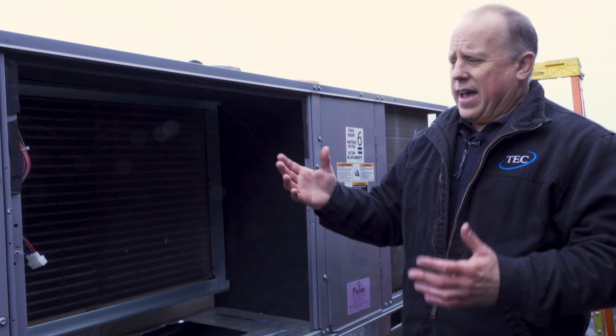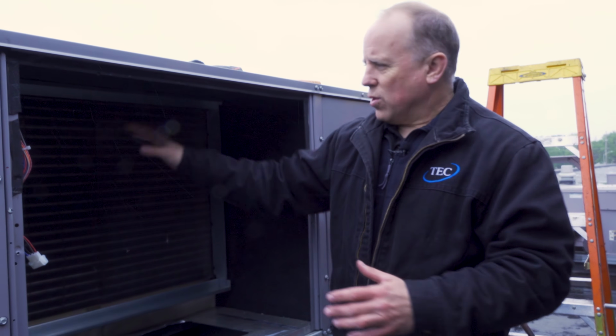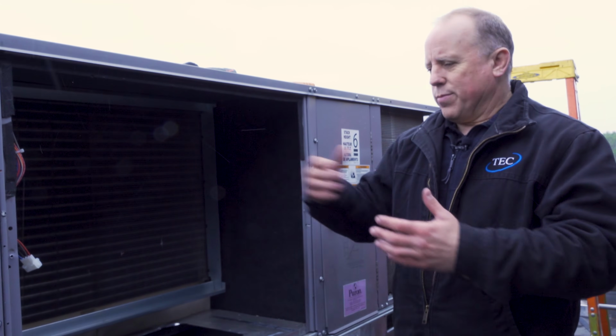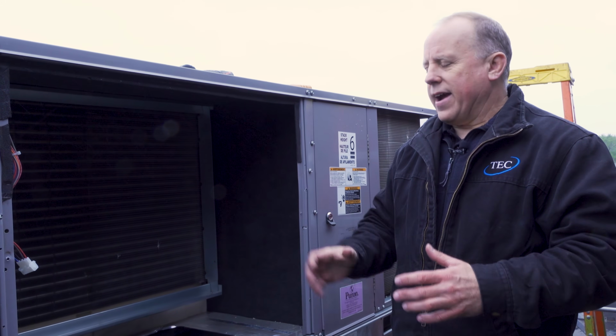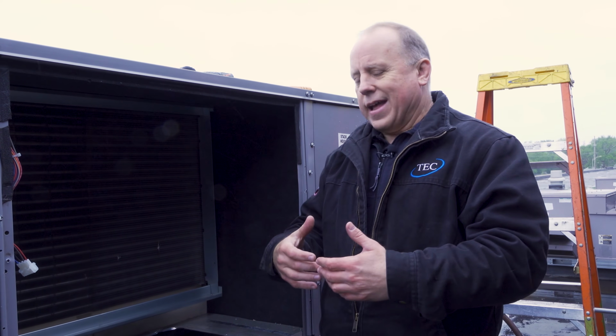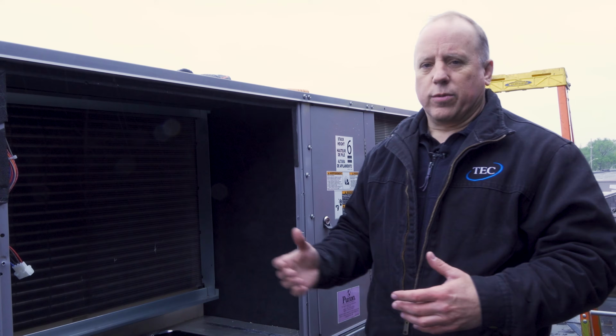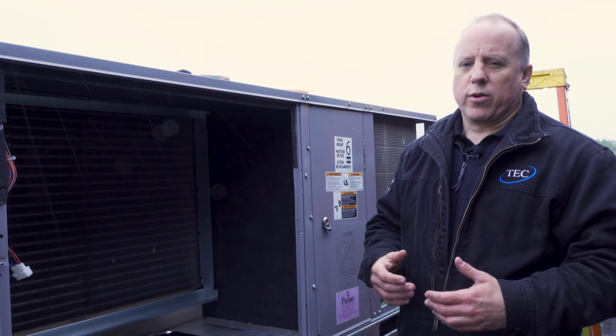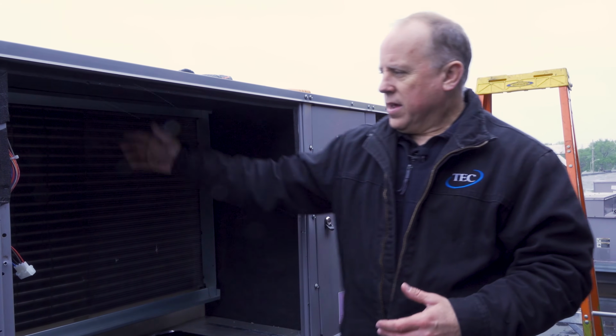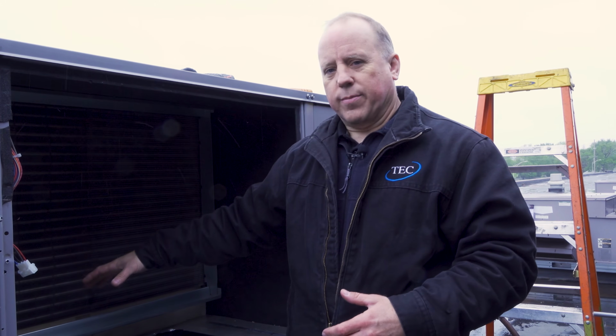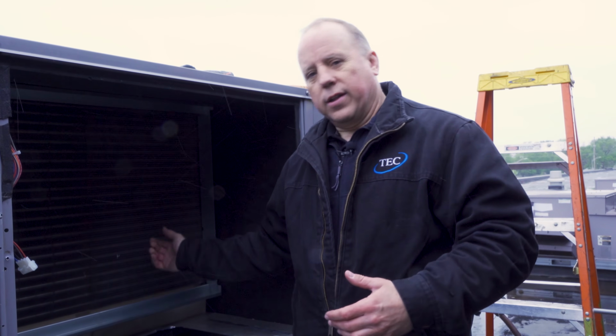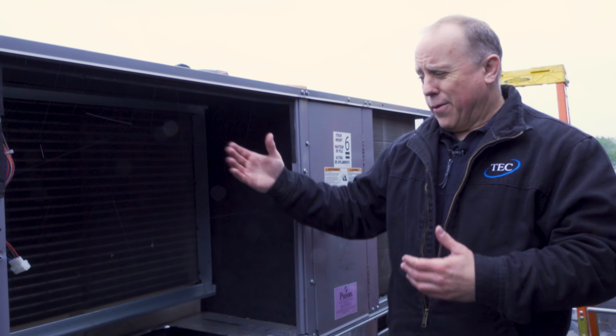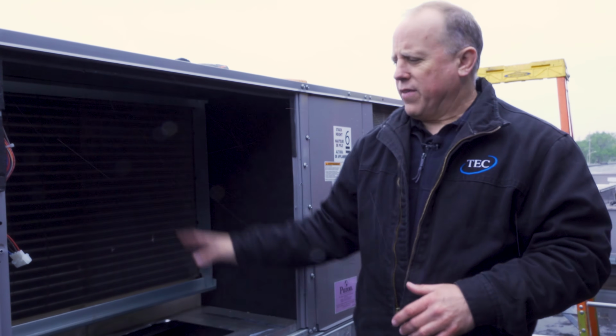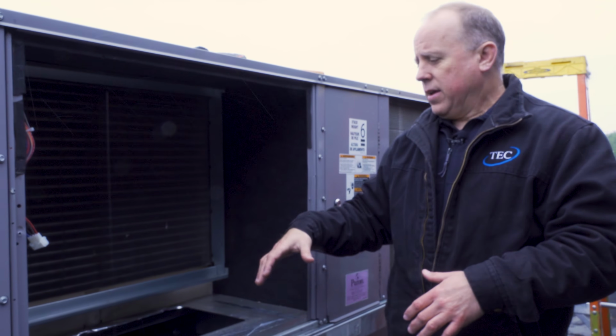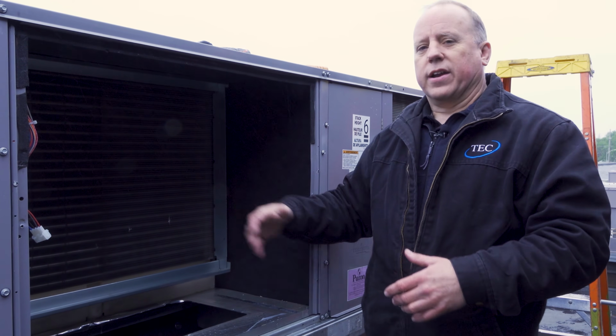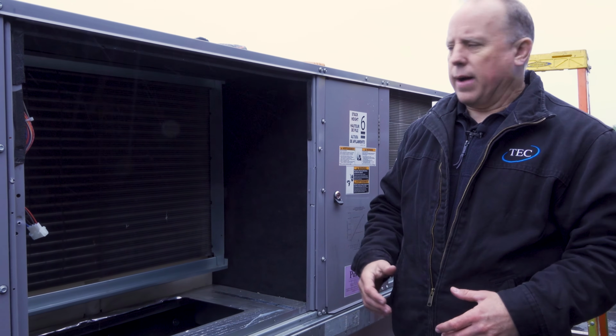So in that case, I would take it the same way. I'd soak down my coil. That would break down any grease and debris on there. And then I would just, in that same bottle, or a different bottle, whatever I want to use, just use water to rinse it down carefully, because I'd want that to drain right into my drain pan, off the coil and out of the unit. I want to be careful that I don't have any of this dripping down into the unit itself, which is then going to drip down into the building and cause a problem.